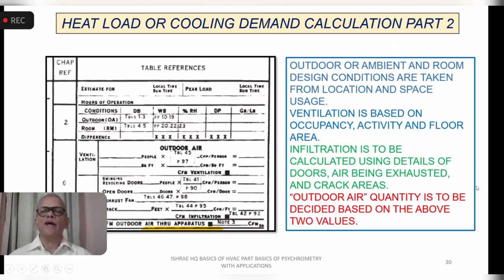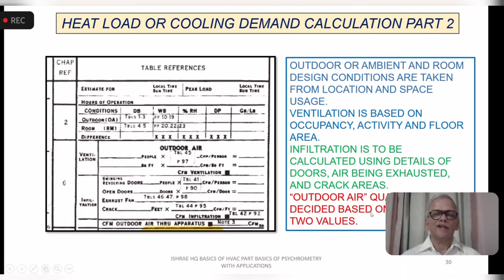This is the outdoor air and ambient condition, and the room design conditions are taken from this. Ventilation is calculated from this. Infiltration also is calculated. And then the outdoor air quantity is decided using these values. So that's a part of the load calculation. So you know the outdoor air, or fresh air, to be added. You know the sensible heat to be removed.